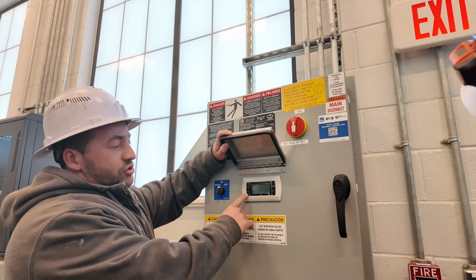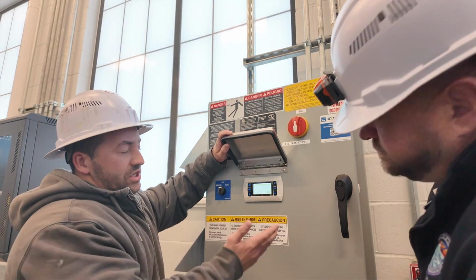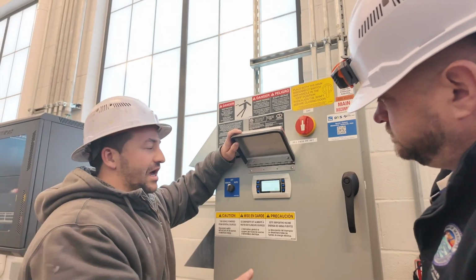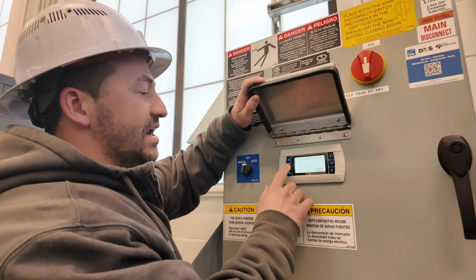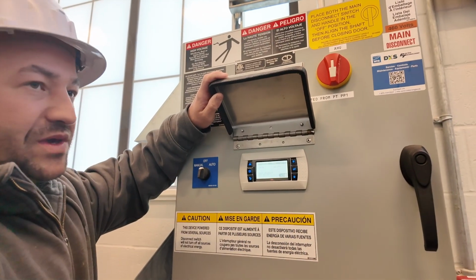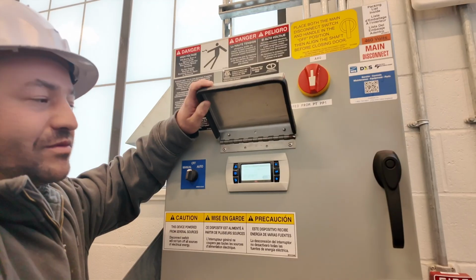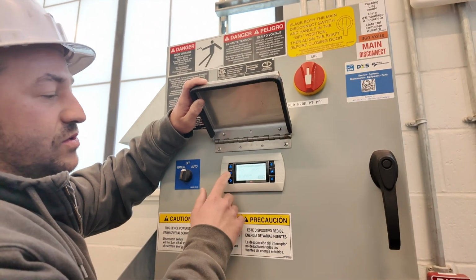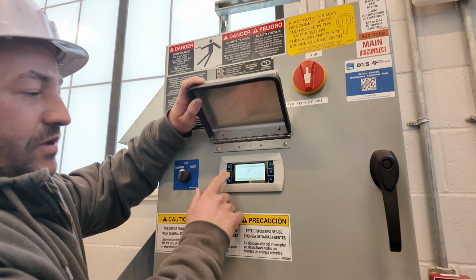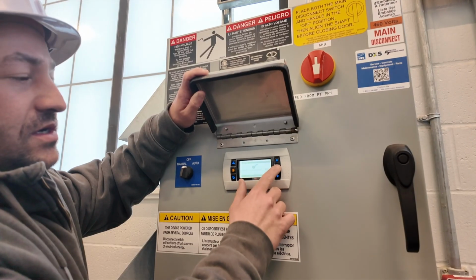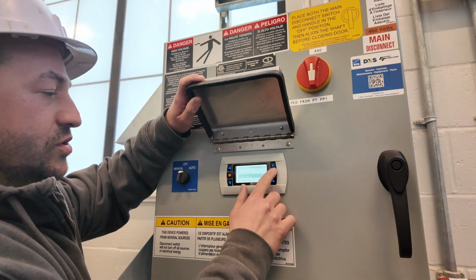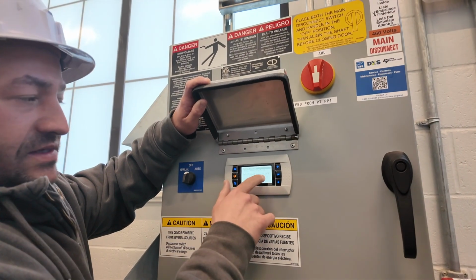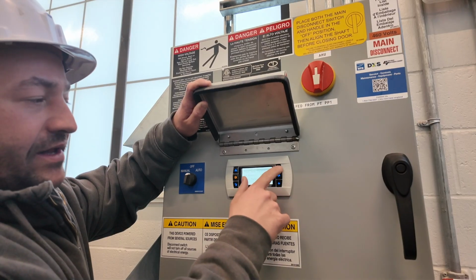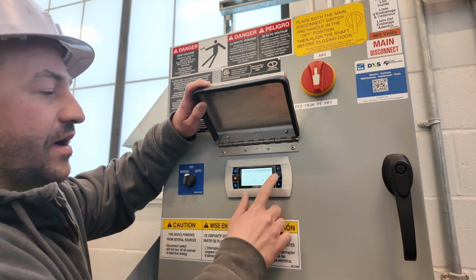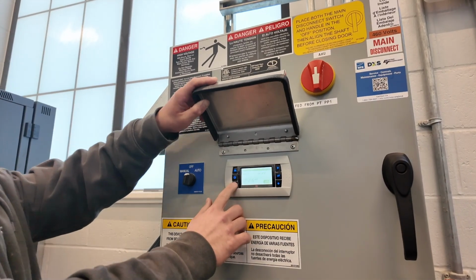This is the actual controller that will display basically what the unit's doing at the moment in time, leaving air temperature. If you need to change the set point, once the BMS is communicating back and forth, it'll show you with the BMS. If you wanted to do it from the front end there, click the bullseye, insert password 2100. Then config, set point, and just highlight it, and just up and down to adjust it. I did write the password.